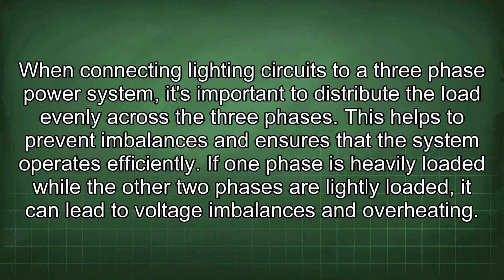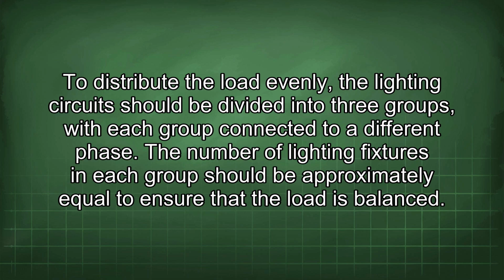This helps to prevent imbalances and ensures that the system operates efficiently. If one phase is heavily loaded while the other two phases are lightly loaded, it can lead to voltage imbalances and overheating. To distribute the load evenly, the lighting circuit should be divided into three groups, with each group connected to a different phase. The number of lighting fixtures in each group should be approximately equal to ensure that the load is balanced.